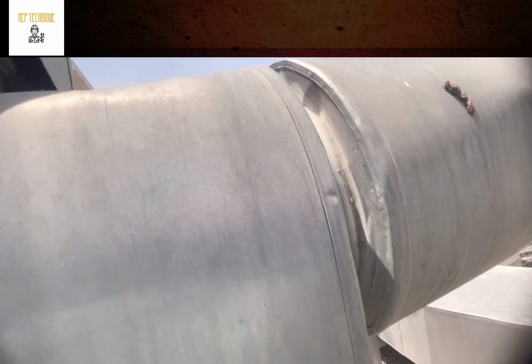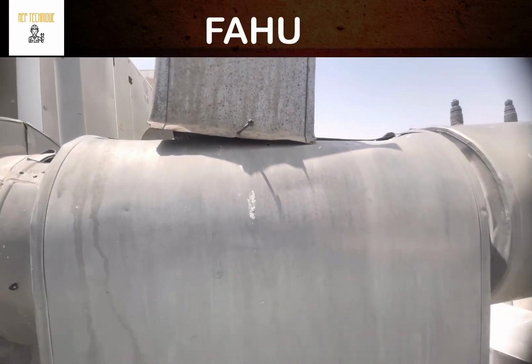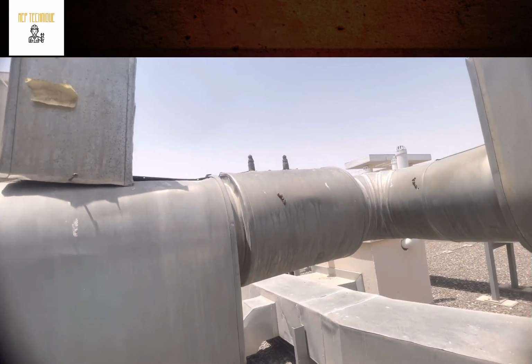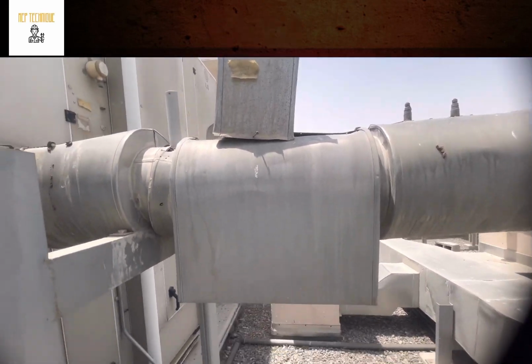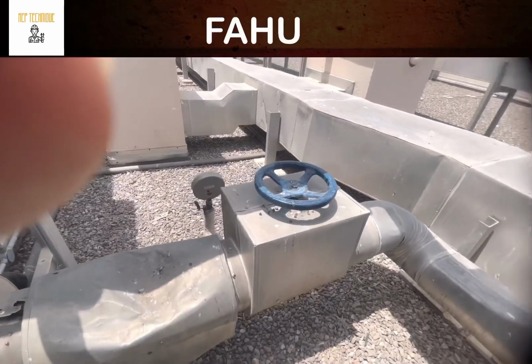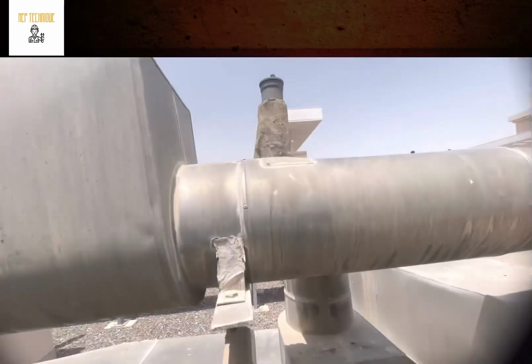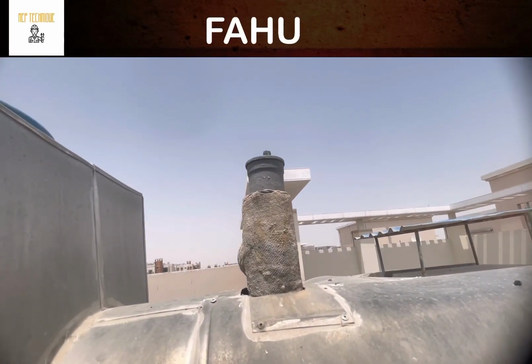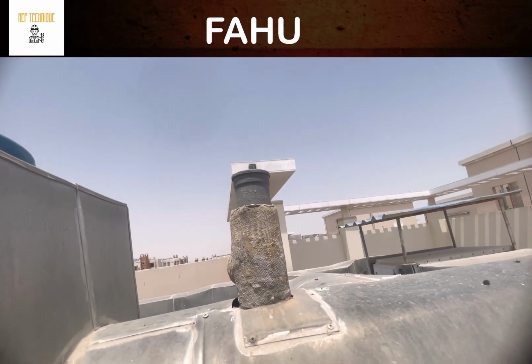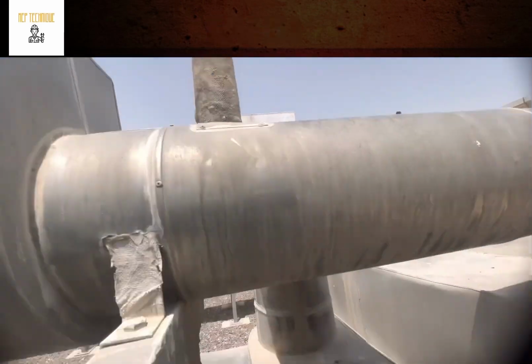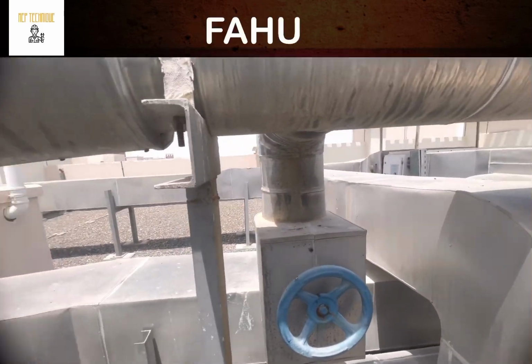The most important thing while controlling chilled water is balancing. We need to balance the chilled water by the DRV, double way regulating valve, then we control it by the actuator valve, and we can isolate and regulate by the butterfly valve. This is the air vent. The air will be released by this air vent automatically. So this is the chilled water distribution.